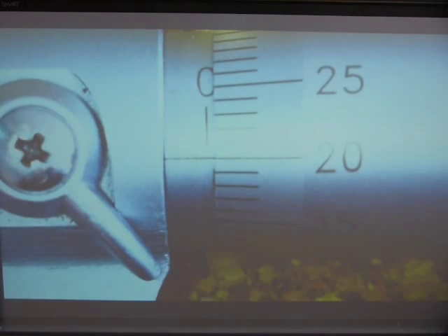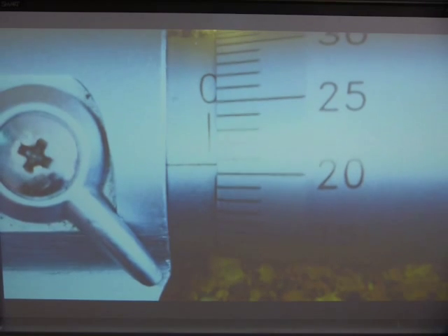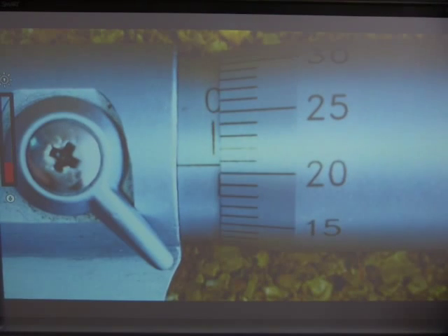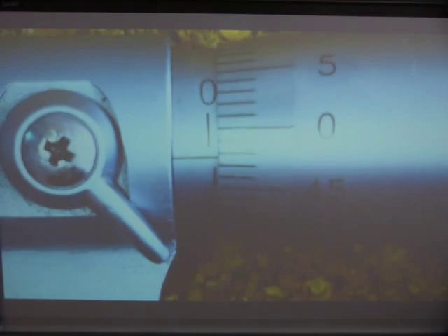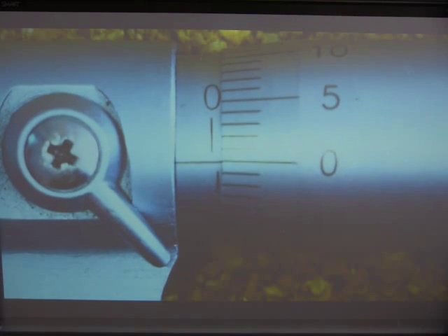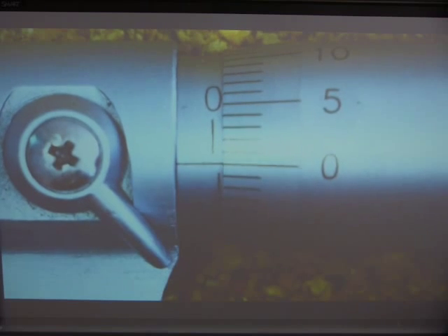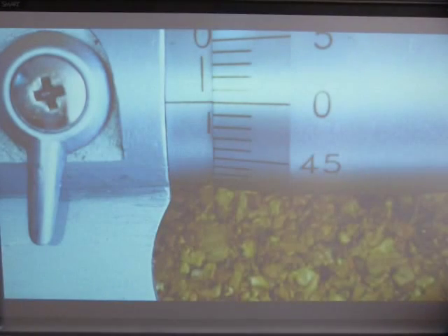Okay, back to the numbers. I'm just going to zoom out a little bit. So that would be two tenths there, or 0.2, 0.21. You get the idea. 0.3, 0.4, 0.49 is there, that's 0.49. And that reading where I'm going to lock it, that would be 0.5, or half a millimeter.